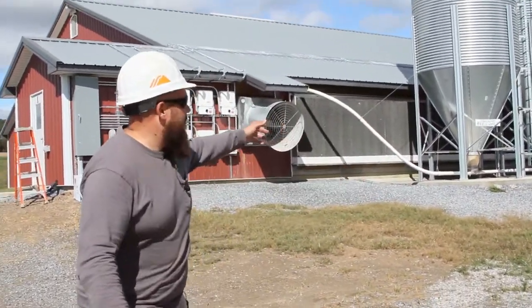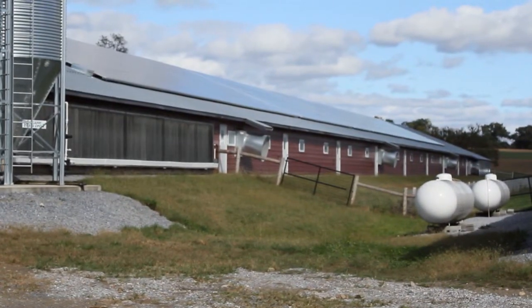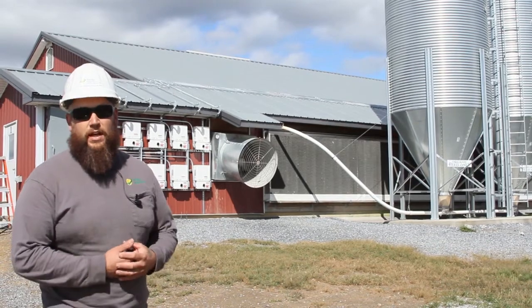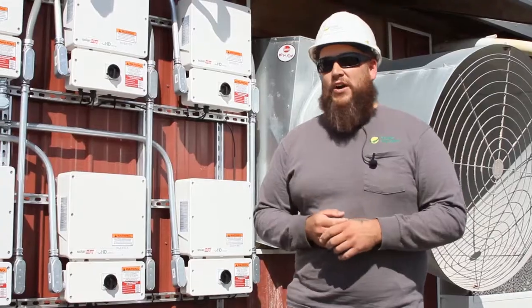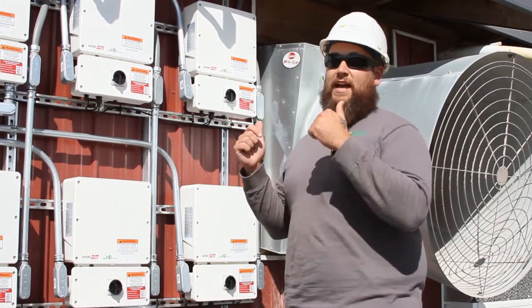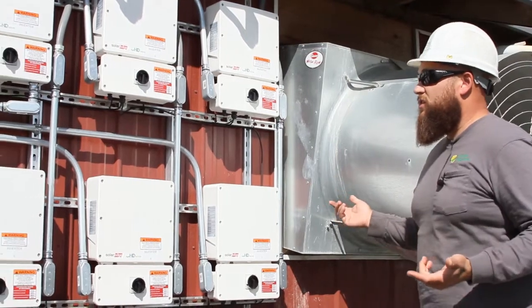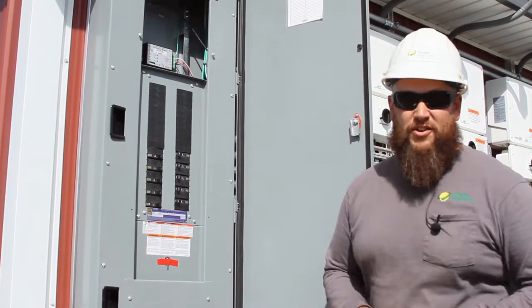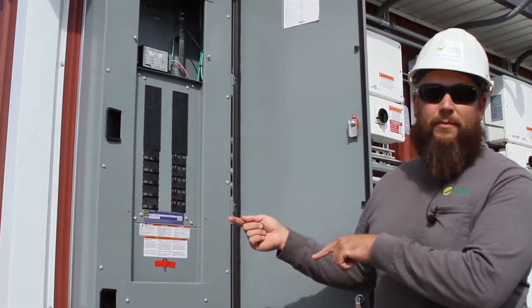Obviously the panels are on top of this chicken barn here. It made the most sense for the interconnection point of our system to help with the cost savings for the customer for wire. So we have 396 AXITEC 330 panels on the roof. That DC power comes down to our nine SolarEdge inverters here, and then it inverts to AC power, cranking out about 412 amps through this combiner panel.